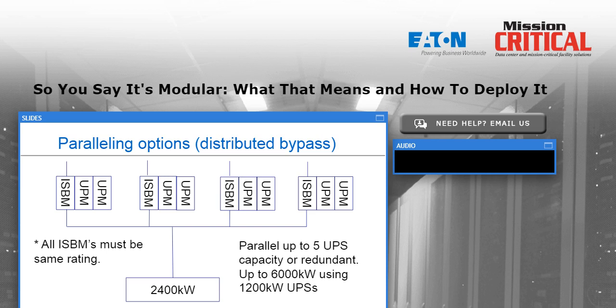So it is a subjective question, and different vendors may tell you different things. But in general, if I've got a battery that's around 2 years old and I want to expand that battery system, it's okay to bring in new batteries. You want to make sure generally that they're from the same vendor and the same battery model, or at least if you can check with the vendor if they're the same impedance, I can parallel multiple strings of batteries.